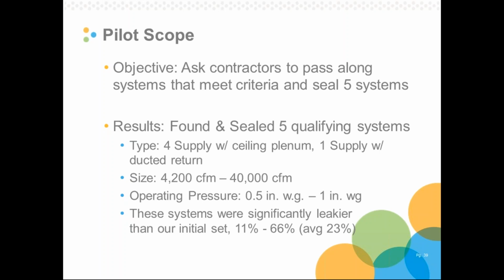We had 5 supply systems. 4 of them had ceiling return plenums. 1 was fully ducted. They ranged about an order of magnitude in size, from about 4,000 CFM, our minimum, up to 40,000 CFM, and they had operating pressures between about 1/2 inch and 1 inch of water.